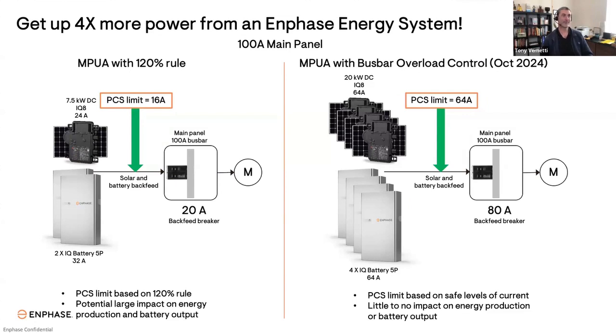And lastly, we've got a comparison of solar and batteries on a 100 amp main panel. With the current version of PCS, the limit again is 16 amps for a 100 amp panel. So this 7.5 kilowatt PV system would get clipped. And the battery, which is rated at 32 amps, wouldn't be able to output its full power. It would be basically half its potential power. So customers like those in California wouldn't get the full potential savings.